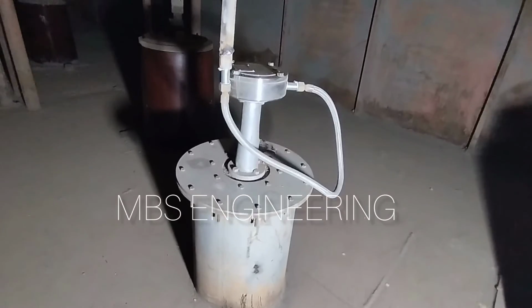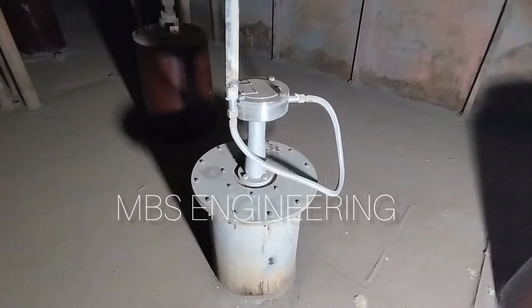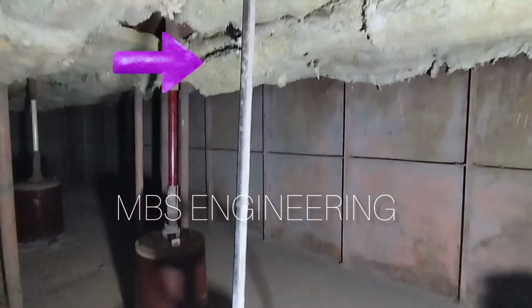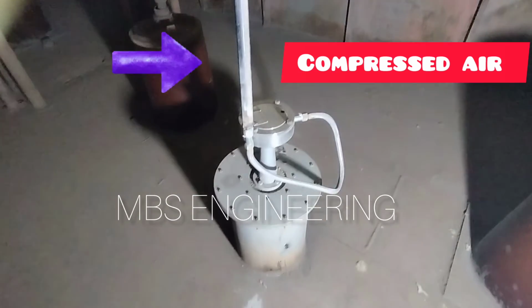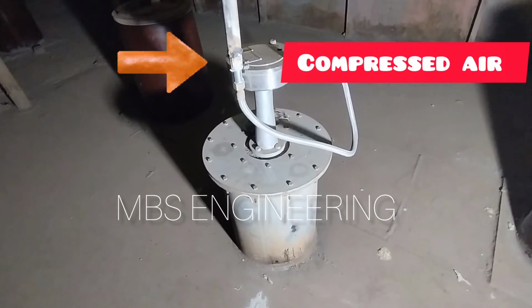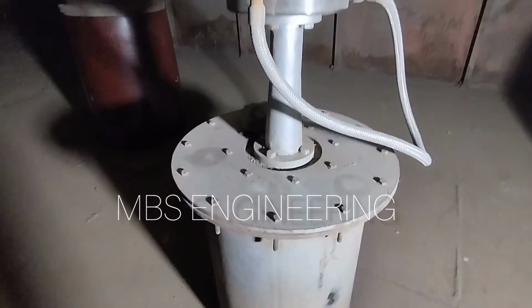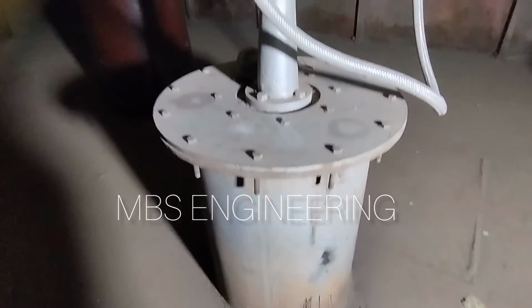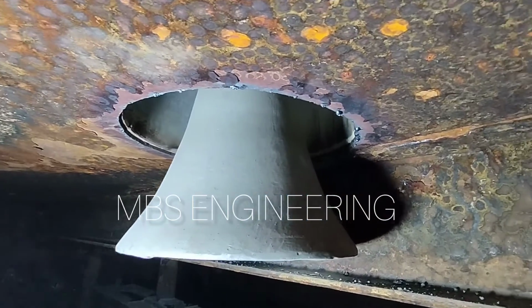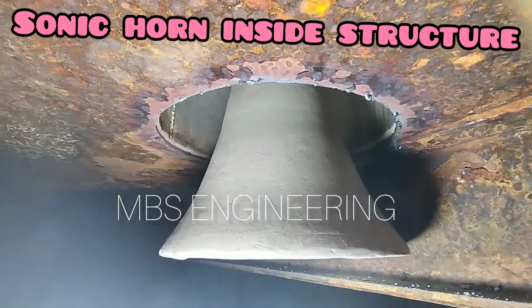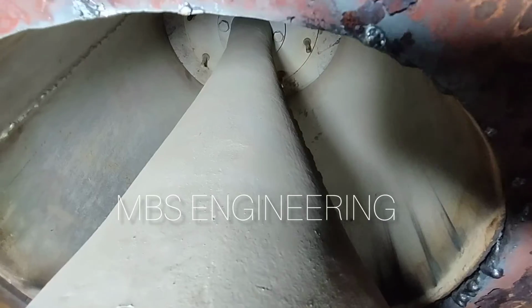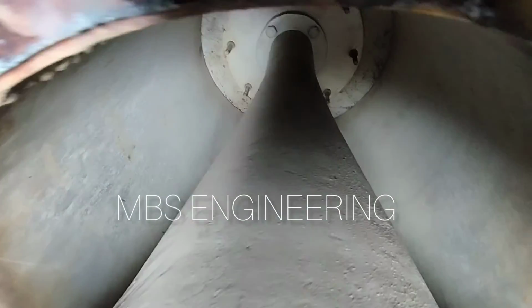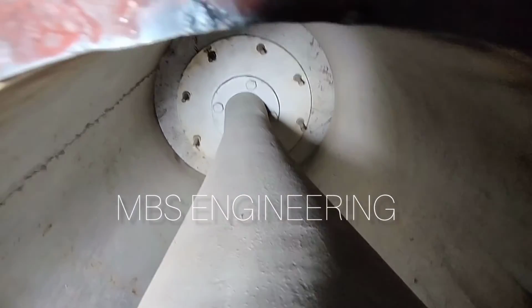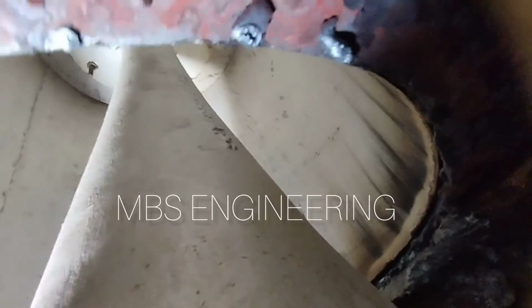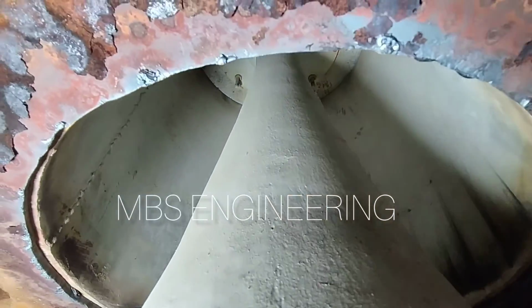A sonic horn produces and amplifies low-frequency sound vibration at high intensity to prevent dust buildup. Sound energy is converted into mechanical energy that fluidizes the dust, preventing it from dust accumulation and buildup that hampers the operation efficiency of the equipment. Sonic horn is pneumatically operated. When the compressed air enters the sound generator, a titanium diaphragm in between its cover and base of the sonic generator vibrates and produces low-frequency sound waves, 140 to 150 decibels, amplified by its bell structure for several seconds at periodic intervals to fluidize the dust particles. Once dust particles absorb the sonic energy and vibrate, the adhesion force between them is weakened, thus preventing the dust from agglomerating or building up.